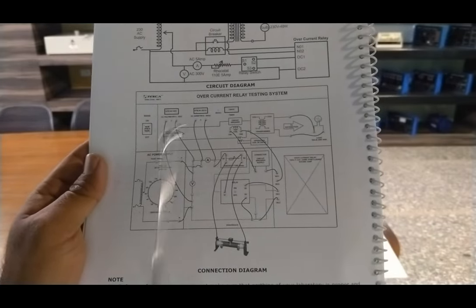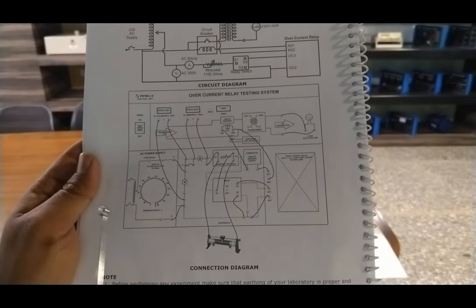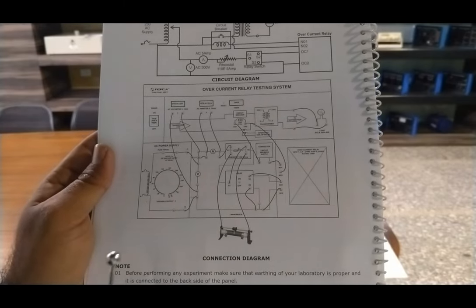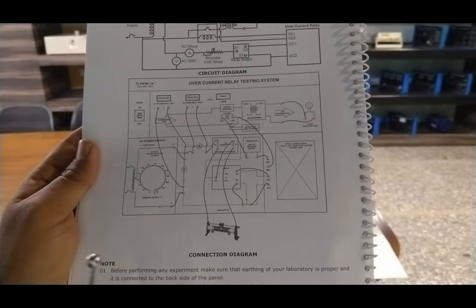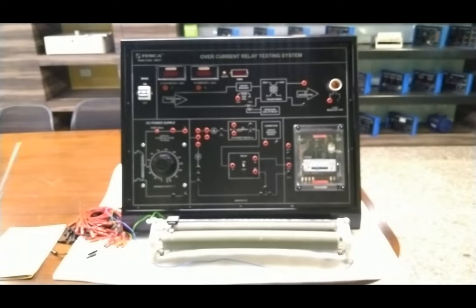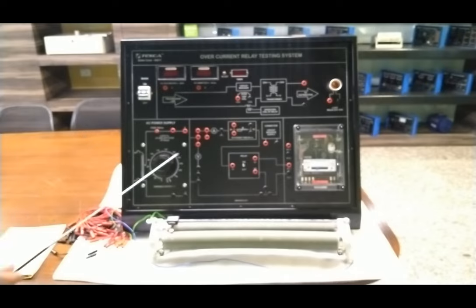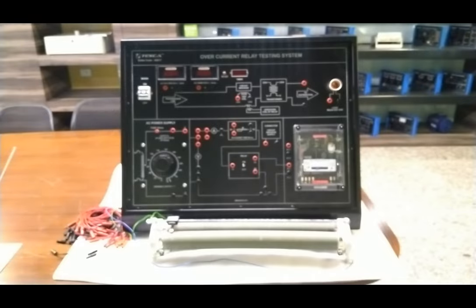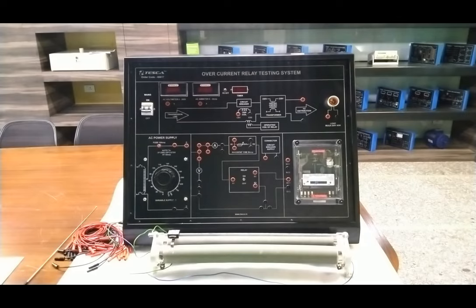All connections are given as per the panel diagram. We have to make all connections as described in the user manual, then follow the procedure given in the user manual so we can easily perform the overcurrent tripping. Before doing the practical, make sure the earthing of your equipment is properly connected to the back side of the panel. Do not touch the rheostat at the time of testing to avoid shock. Always turn the switch to the off position when the relay trips, and the auxiliary supply for the ammeter, voltmeter, and timer should be from a separate transformer.